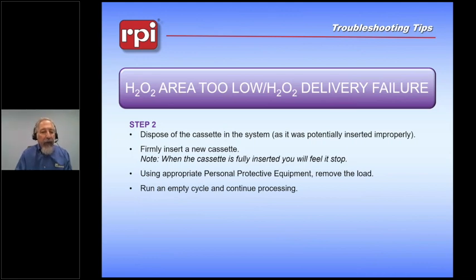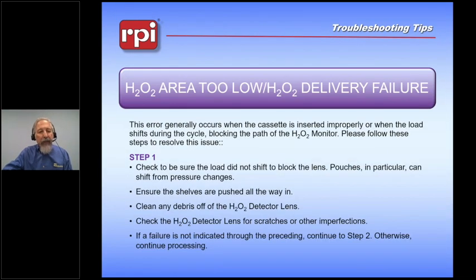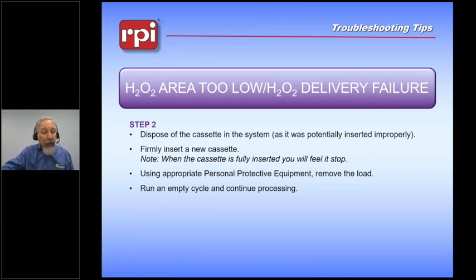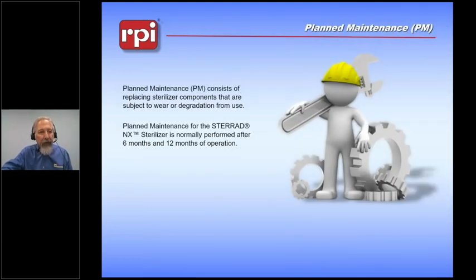The next step, of course, is that if the machine should trigger these errors, we want to be sure that we handle the material properly. So we talk about how we need to remove the load if there is an issue. We will probably need to check the cassette to be sure that it delivered the peroxide properly. Okay, so those are a couple of errors. There are others. We also want to be sure that this machine gets maintained properly. So there are planned maintenances that are set for this system.